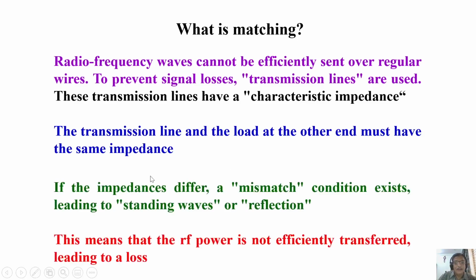the other end, at the probe end, should have the same impedance so that there is no mismatch in the frequency. If there is a difference in impedance, there is a mismatch condition, and we get what is called reflected power, reflection, or sometimes standing waves. What it means is, as I told you earlier, if there is a mismatch of the impedance, all the RF power that you are putting in to generate the exact 90-degree pulse, which you would have calibrated, is not going into the sample. It is not efficiently transferred. It leads to loss of signal. So matching is an important condition.